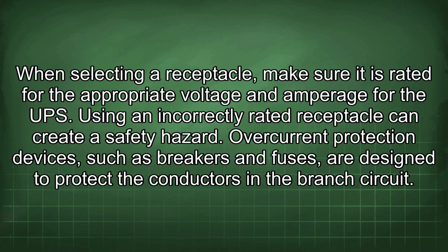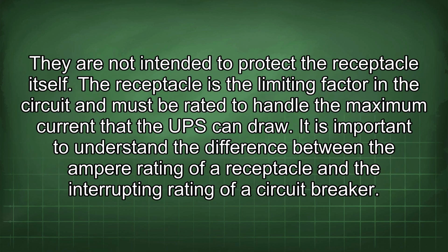Overcurrent protection devices, such as breakers and fuses, are designed to protect the conductors in the branch circuit. They are not intended to protect the receptacle itself. The receptacle is the limiting factor in the circuit and must be rated to handle the maximum current that the UPS can draw. It is important to understand the difference between the ampere rating of a receptacle and the interrupting rating of a circuit breaker.